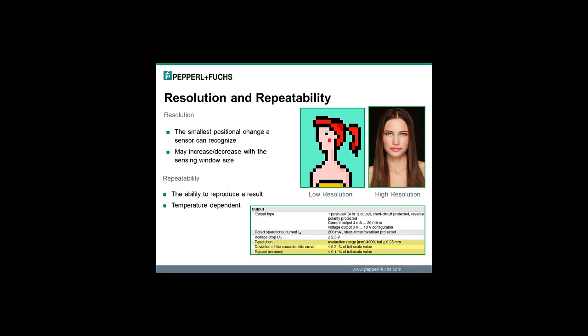You get a much finer look the better the resolution is for a given product. Now, repeatability, that's a little different. The repeatability is the ability to reproduce a given result. So if you go one time out to a target that's 10 inches away, it tells you 10 inches. The next time you go out, it says 10.1. Then there's a 0.1 inch repeatability difference, or plus minus 0.05 inches. So you can look at the spec in the data sheet and see that repeat accuracy or repeatability and find out from measurement to measurement how much you can vary.